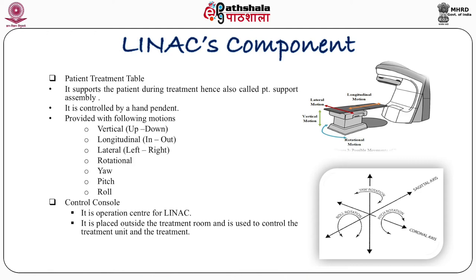The patient treatment table supports the patient during treatment and has many types of movement: vertical up and down, longitudinal in and out, lateral left and right, and rotational movement about its axis. It is controlled by a hand control pendant. The control console is the operation center for the linac, placed outside the treatment room. It is used to control the treatment unit and is considered the heart of the machine. The operation of the linac is controlled from the control room using various controls and switches on the panel.